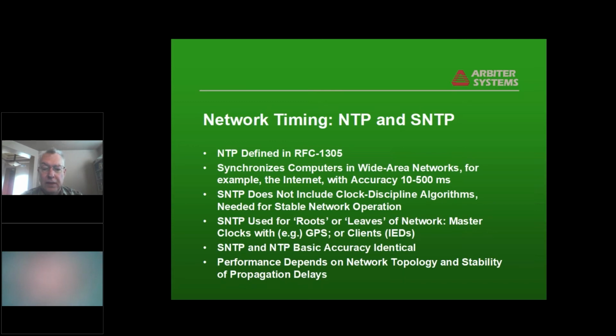and the ability of an intermediary server to receive time from more than one server, the clock disciplining algorithms are quite sophisticated in order to allow it to do that and maintain stability. SNTP leaves all that out, and it's intended for use at what they call the roots and leaves of the network: the very highest level master clocks or servers with, for example, a GPS source, or the lowest level client or slave, like an IED.